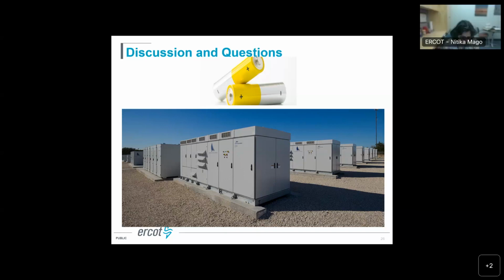So most of the battery fleet that we have today is required to provide primary frequency response. Our frequency deadband is 17 millihertz, and our droop settings can be as low as 1%, so that when our frequency drops to 59.4 hertz, we expect full response from the resources. That's generally the setting most of our storage fleet is operating to.